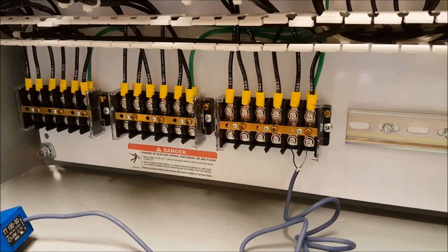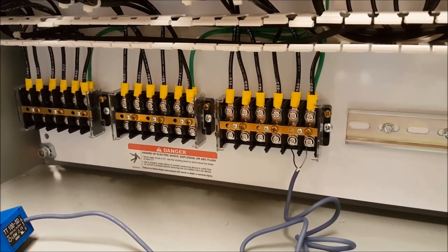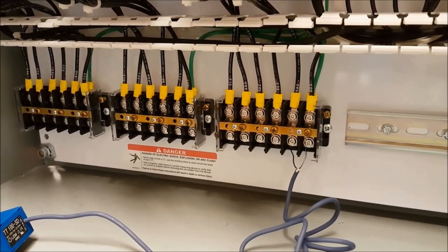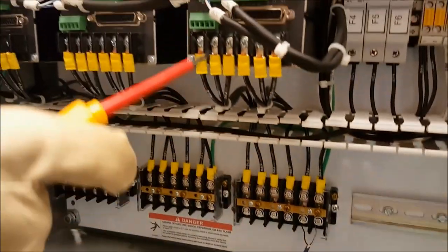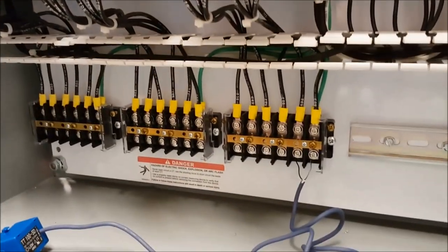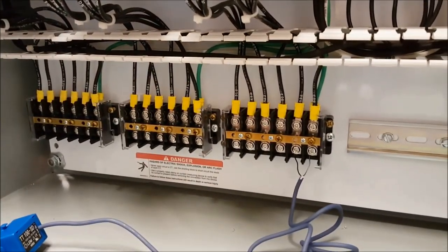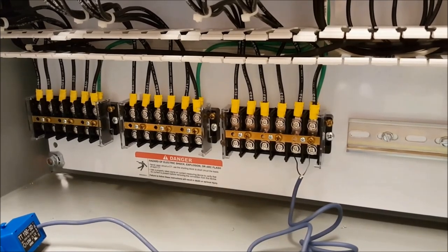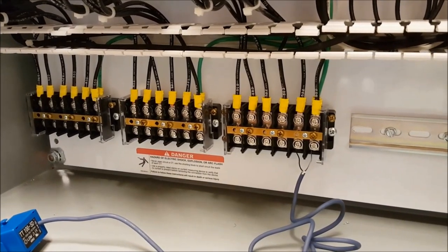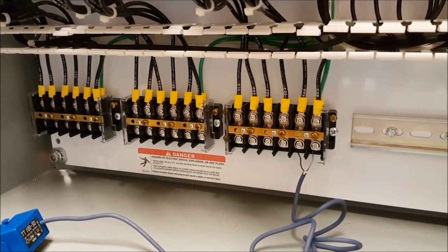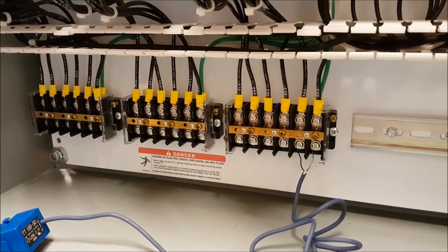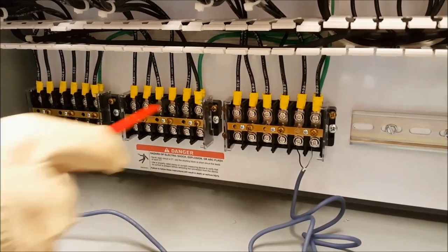In order to safely modify the current transformer wiring at the meter or metering side CT shorting block from here to here, the positive leads of the current transformers must also be shorted out to the CT shorting strip using additional screws, which are usually found on the corners of the shorting block. Here, here, and here.